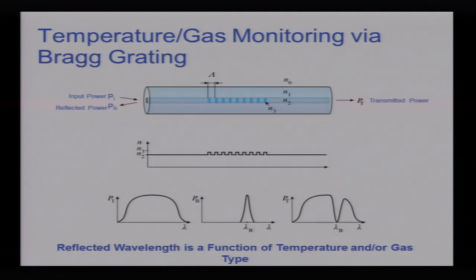Fiber Bragg sensors — this is a neat technology. A Fiber Bragg sensor takes a piece of fiber optic cable and replaces sections of the core of the fiber with sensing elements. These sensing elements can be temperature sensing, pressure sensing, or gas sensing. As the temperature changes, the refractive index of the core of the fiber changes, and I get a reflection back that is directly proportional to temperature, gas, or pressure. Expect to see this used a lot more in the very near future.